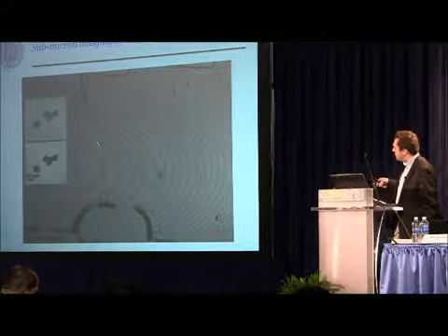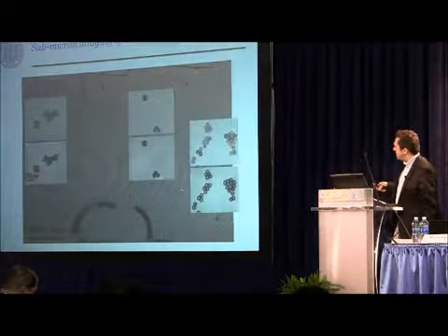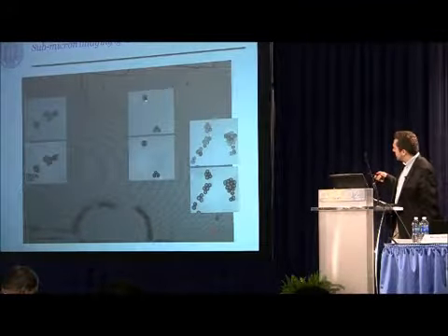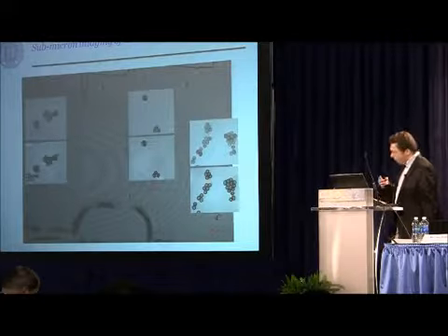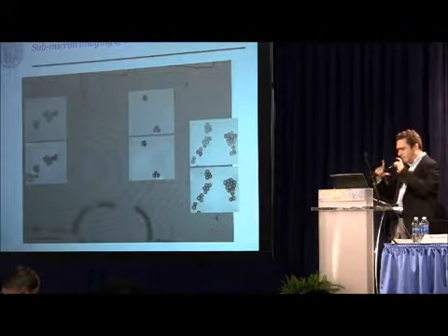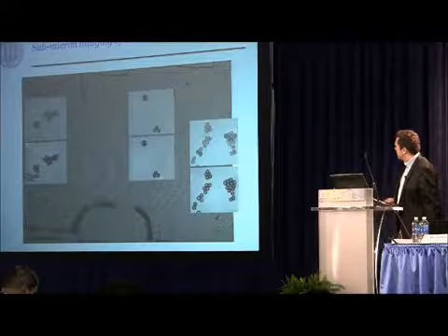So for instance, this is a scale bar of a millimeter. You're looking at 24 millimeters square. And if you digitally zoom into different parts of this image, you'd be seeing this monolayer of blood cells. This is actually a granulocyte, and it has some nuclear features inside, and these are red blood cell clusters, so that you get a very large field of view with a distinct submicron resolution. Also, that comes within a very compact, like less than 100 gram, instrument.